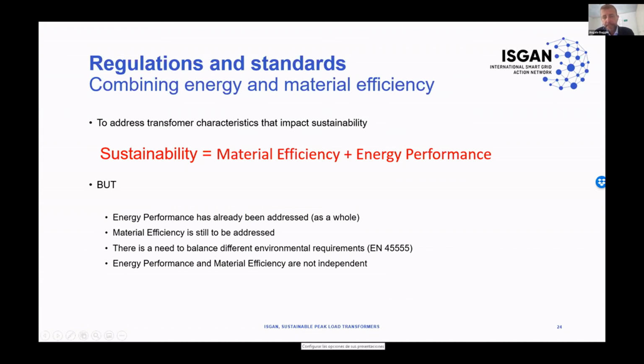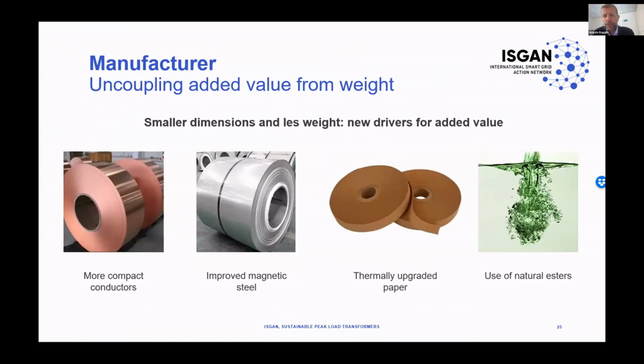Next one, please. And this was the conclusion in the perspective of regulation and standardization, the need of higher material efficiency. And in the perspective of the manufacturer, in my opinion, this is good again. We need it, because with the current approach, the added value of the transformer is squeezed by the weight of the material to be used, with a limited room for new technologies. Dual nameplate or better peak load transformers could allow an uncoupling of added value from transformer weight. That is, smaller transformers do not necessarily mean lower revenue for the manufacturer.